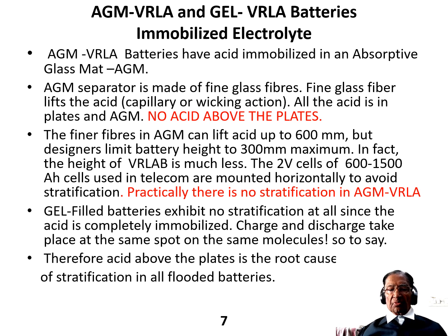Now, AGM VRLA and gel VRLA batteries have immobilized electrolytes. So this is the advantage. These have lesser stratification, or practically no stratification, compared to the flooded battery. The AGM, for comparison, you should know the difference. That's why I have presented this.